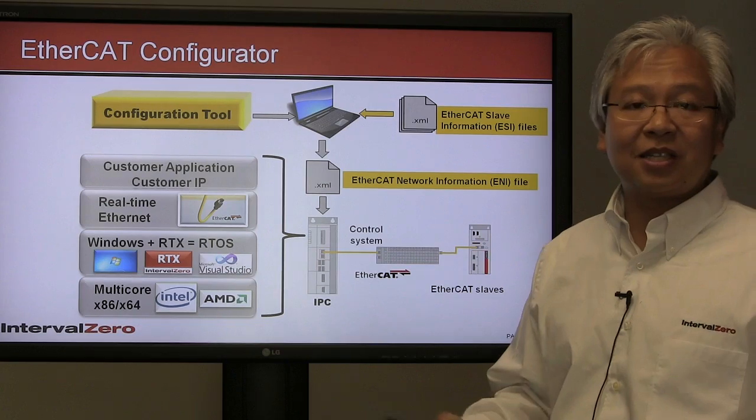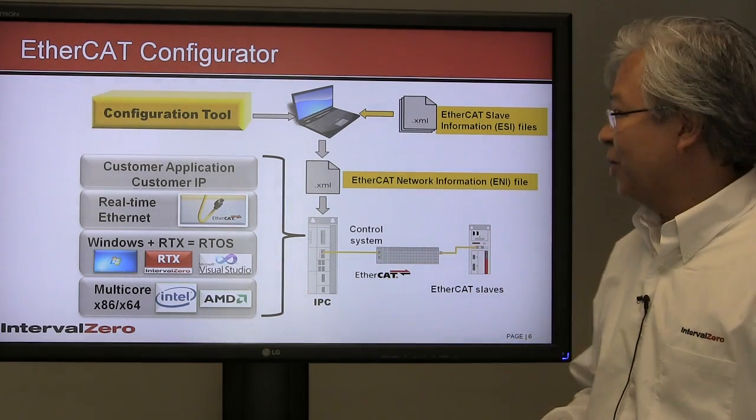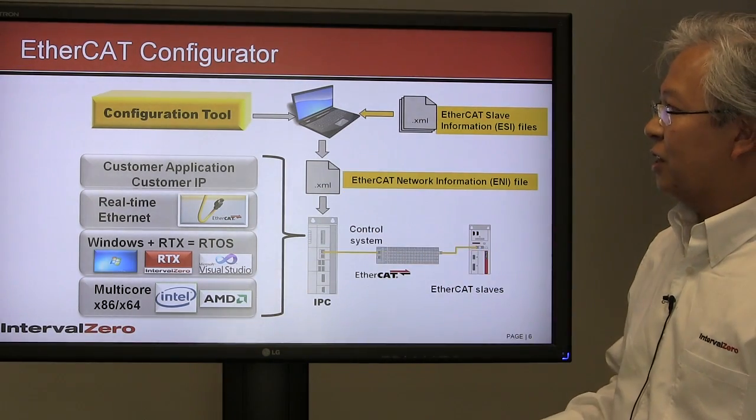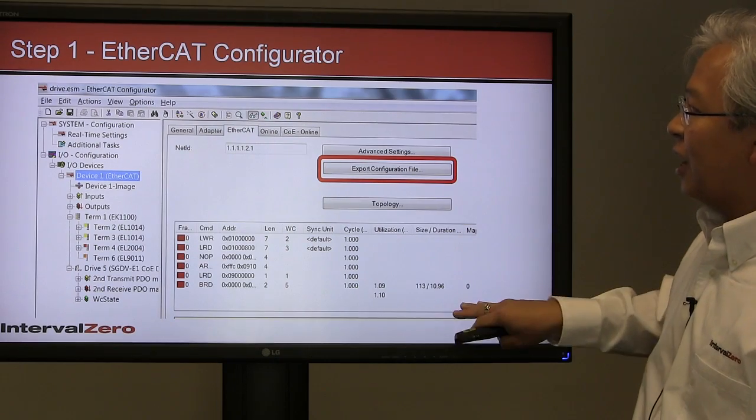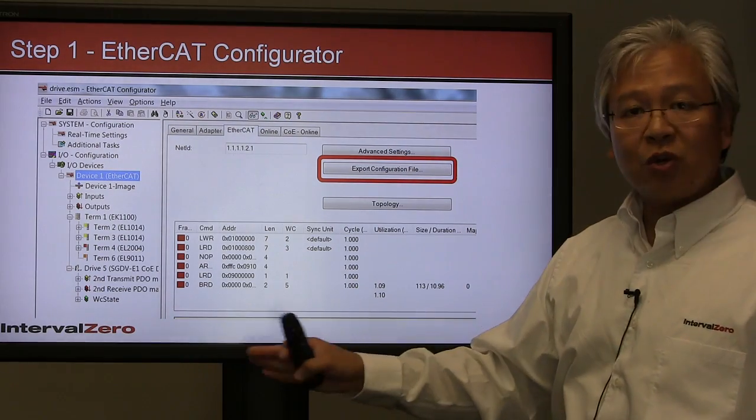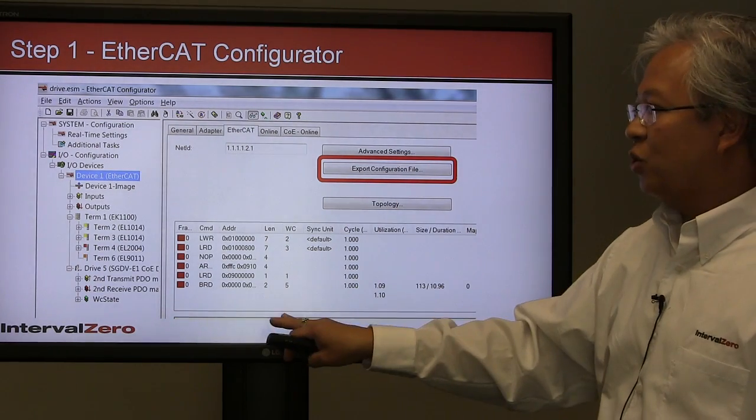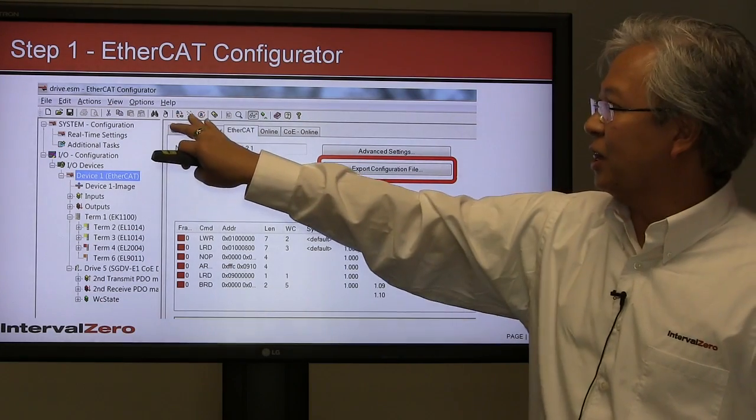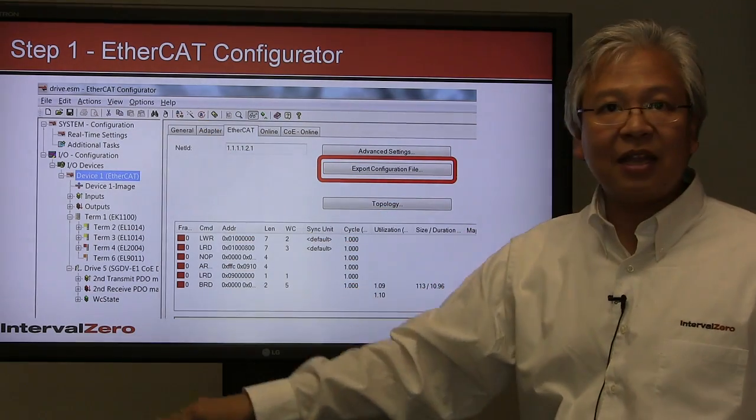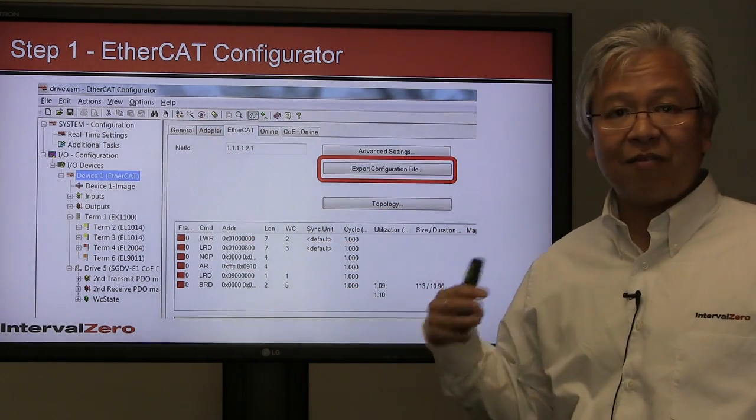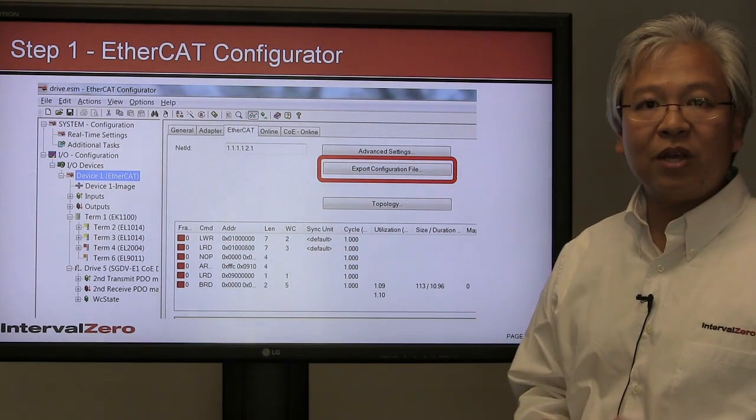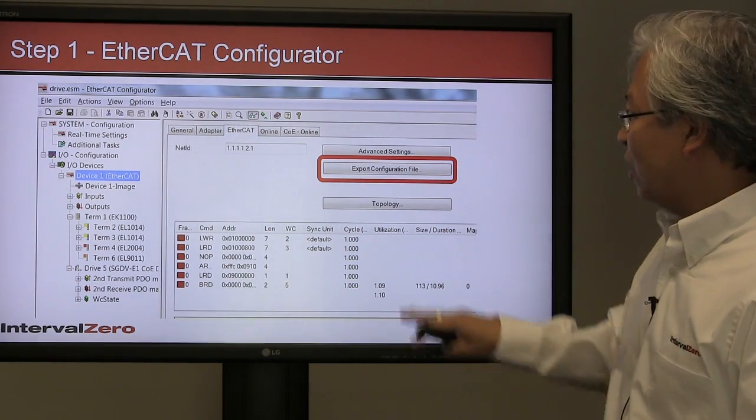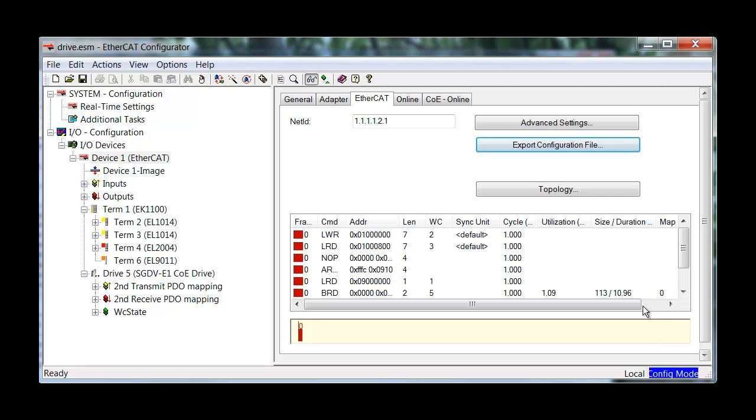This is the EtherCAT configurator. After you do all your installation, you'll open up this tool. At the beginning, you'll click the button to survey the entire network. Using the CAT5 cable, it will go out and query the entire EtherCAT network. Then you're going to export configuration—that ENI file will be exported and saved to a location you can remember.